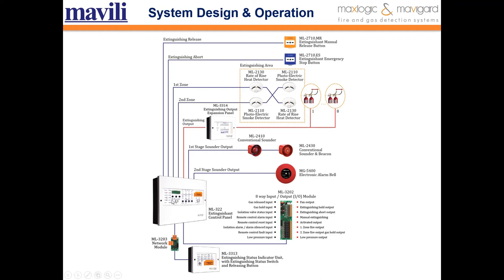In the system design, the extinguishing control panel is connected with a conventional sounder for the first stage — this is the pre-alarm stage. We use conventional sounders or conventional sounder beacons. For the second stage, when the extinguishing process starts and the tubes are releasing, the second stage sounder rings.